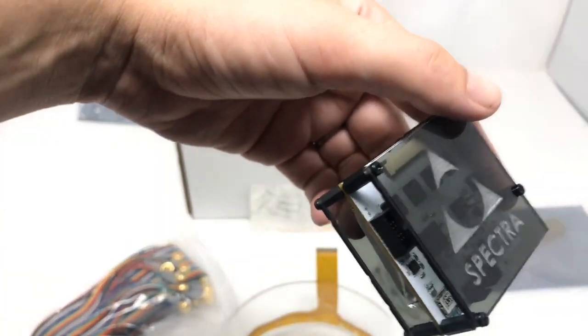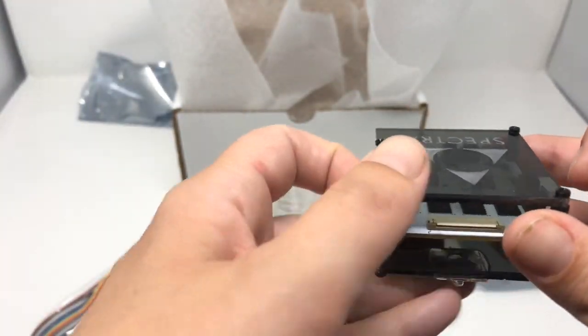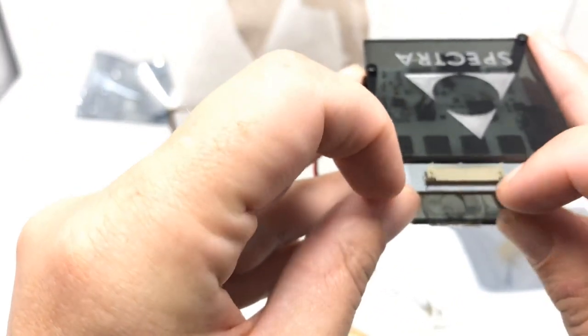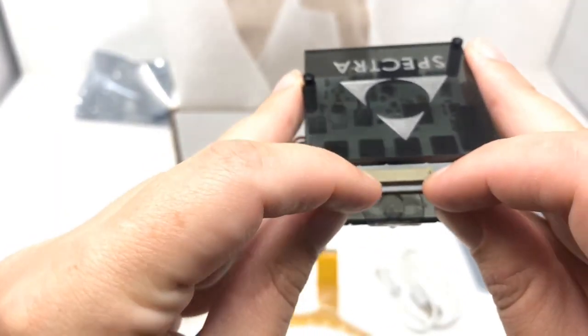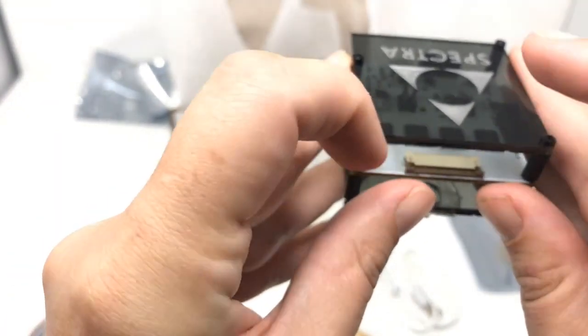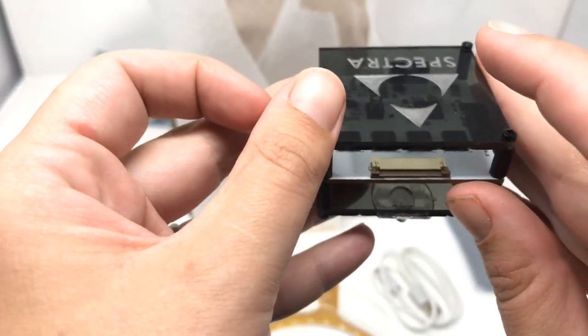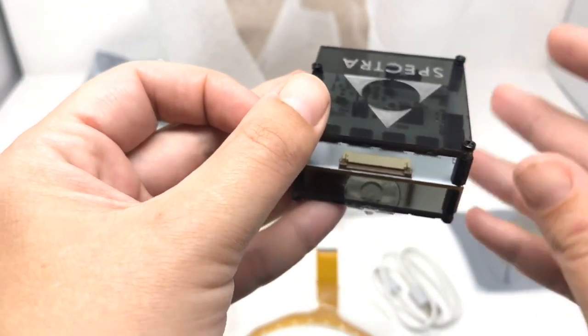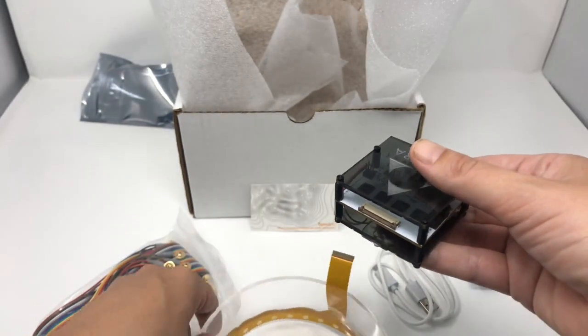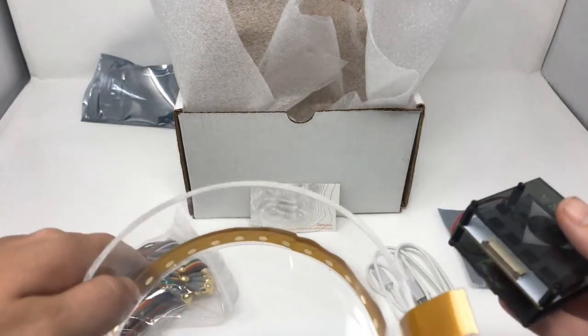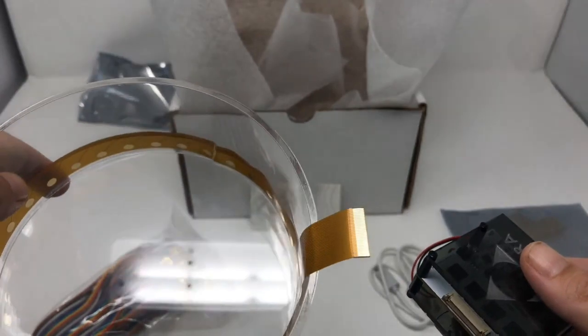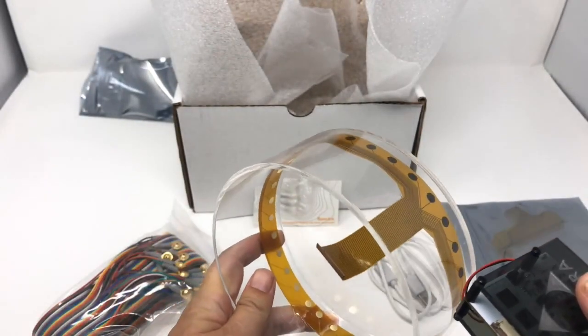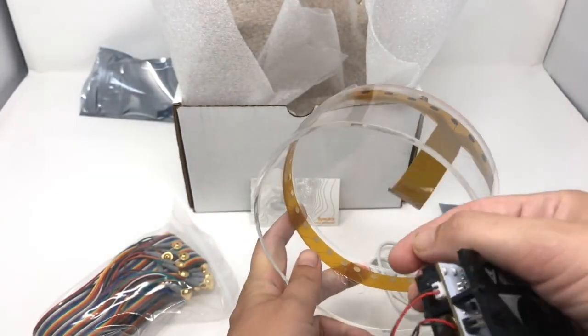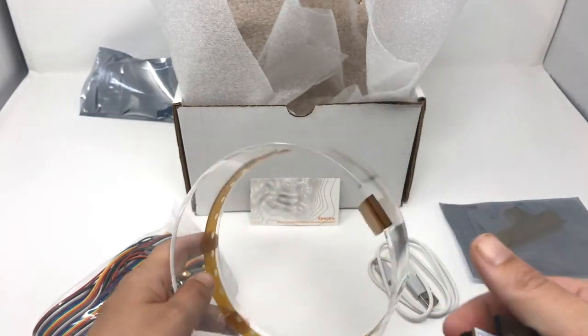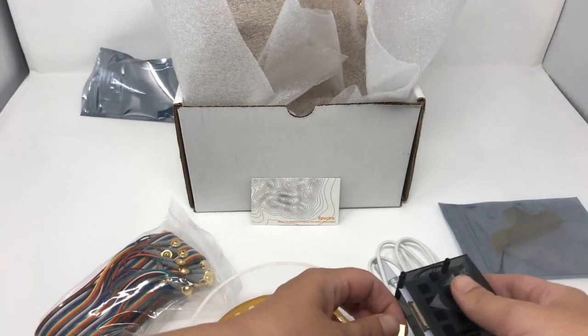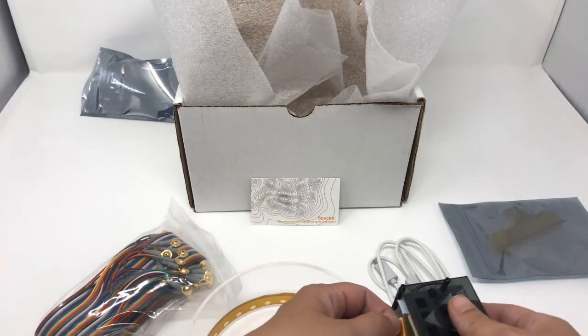So what we do is we have a little look in here. You'll see two tabs that you can pull down. That opens up the FPC connector and makes it ready for cable insertion. Here is the 32 electrode array. It's got a gold-plated side and a dark side. Simply grab the gold-plated side so it's on top.